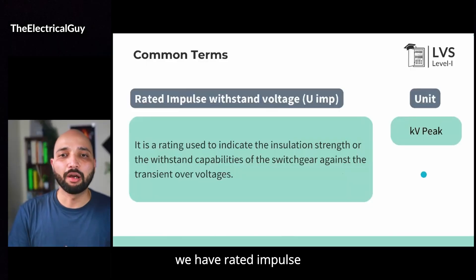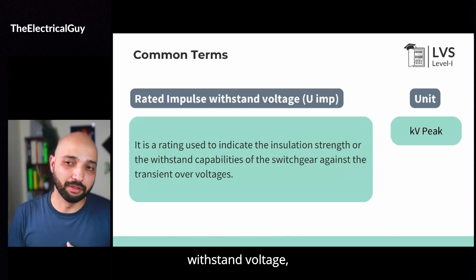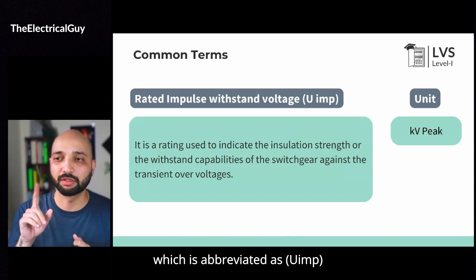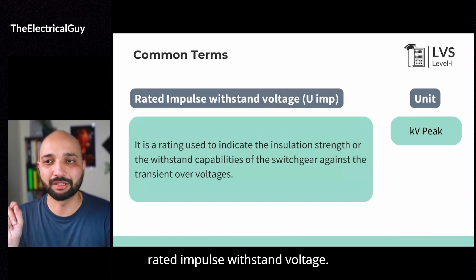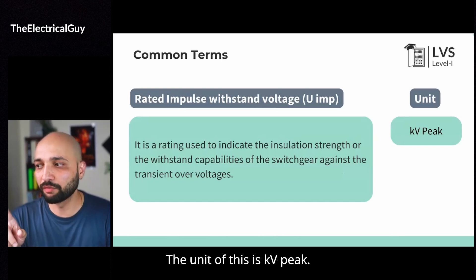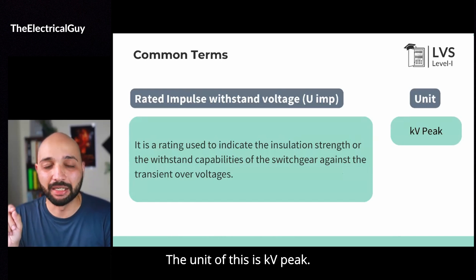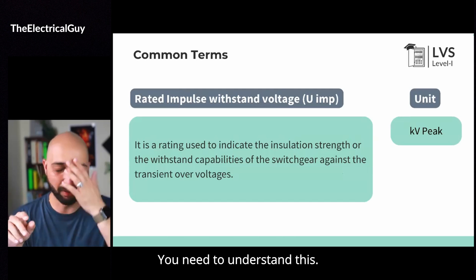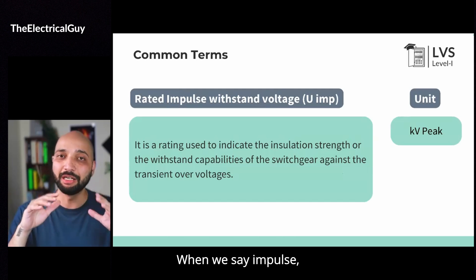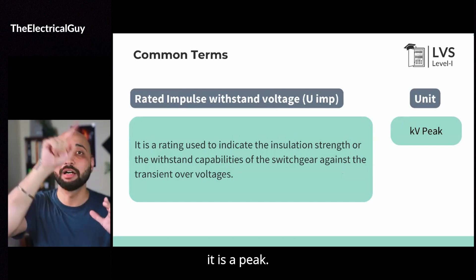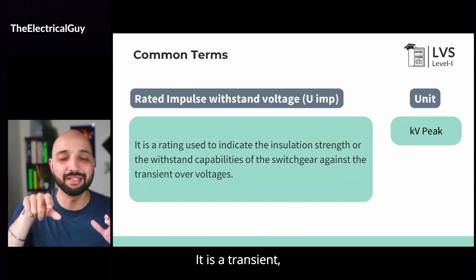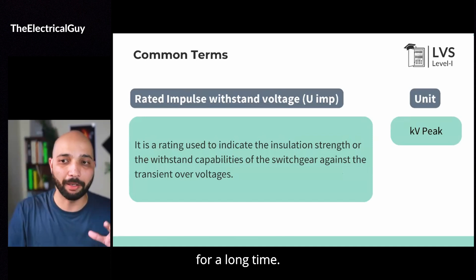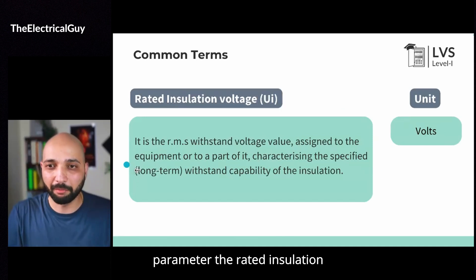Then moving on, we have rated impulse withstand voltage, which is abbreviated as UIMP. The unit of this is kV peak. Now why peak? When we say impulse, it is a peak value. It remains in the system for a very short time — it is a transient, it will not remain for a long time. But when we saw the previous parameter, the rated insulation voltage, it is there for a long time.